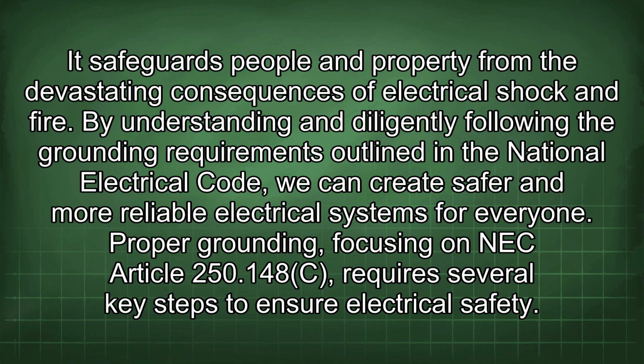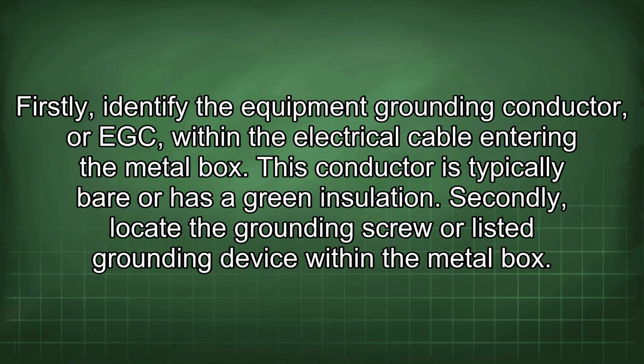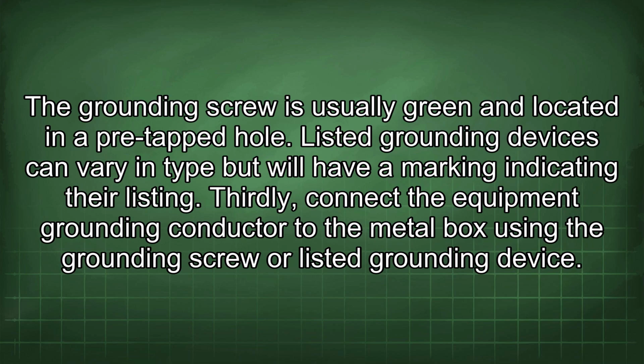Proper grounding, focusing on NEC Article 250.148(C), requires several key steps to ensure electrical safety. Firstly, identify the equipment grounding conductor, or EGC, within the electrical cable entering the metal box. This conductor is typically bare or has a green insulation. Secondly, locate the grounding screw or listed grounding device within the metal box. The grounding screw is usually green and located in a pre-tapped hole. Listed grounding devices can vary in type but will have a marking indicating their listing.